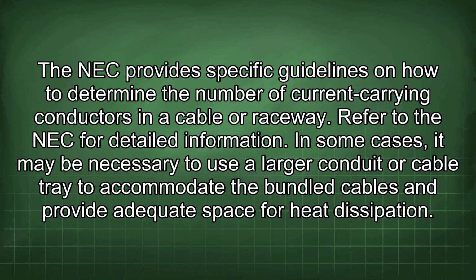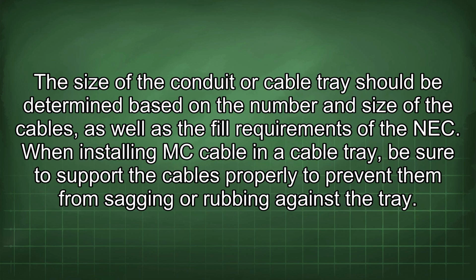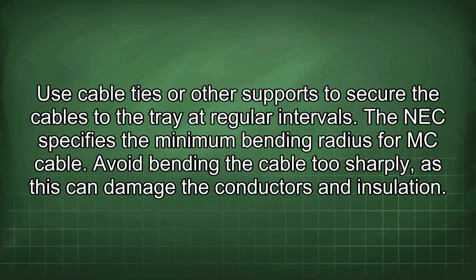In some cases, it may be necessary to use a larger conduit or cable tray to accommodate the bundled cables and provide adequate space for heat dissipation. The size of the conduit or cable tray should be determined based on the number and size of the cables, as well as the fill requirements of the NEC. When installing MC cable in a cable tray, be sure to support the cables properly to prevent them from sagging or rubbing against the tray. Use cable ties or other supports to secure the cables to the tray at regular intervals.